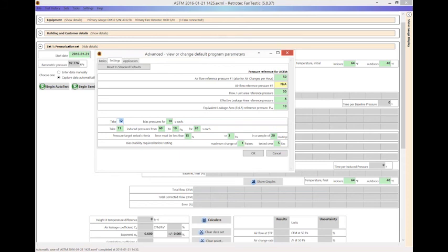So instead of taking 12, I'm going to ask it to just take one baseline for 5 seconds. And if you're learning this, it does help to actually modify some of these things so you understand what the parameters are that you normally have. So I'm going to just tell it to take 3 points, all right? And I'm going to just reverse it so it doesn't get so loud too quick. I'm going to have it go from 20 pascals to 60 pascals.